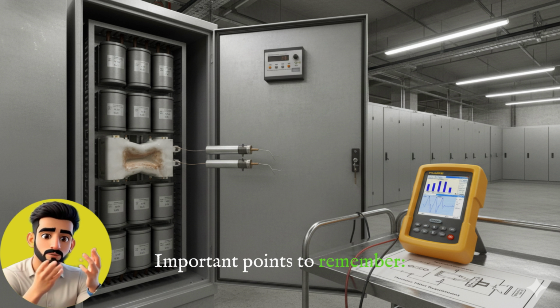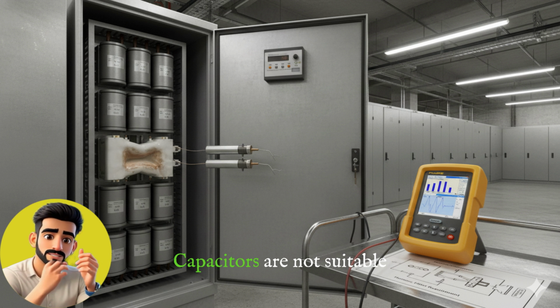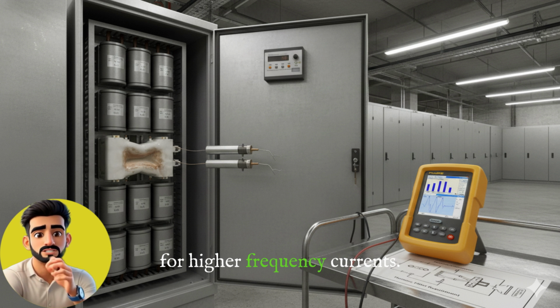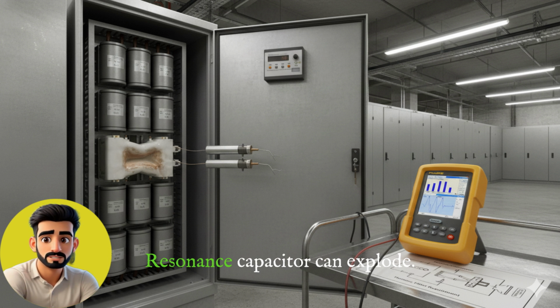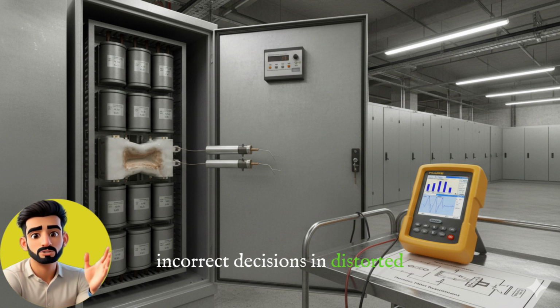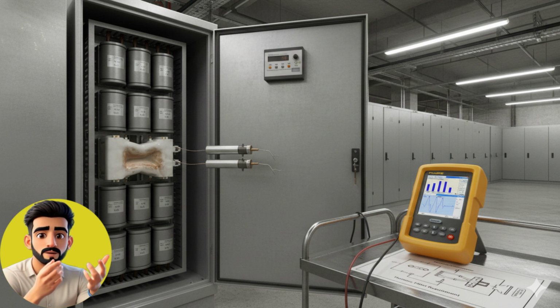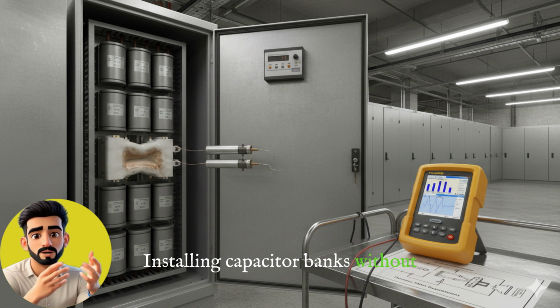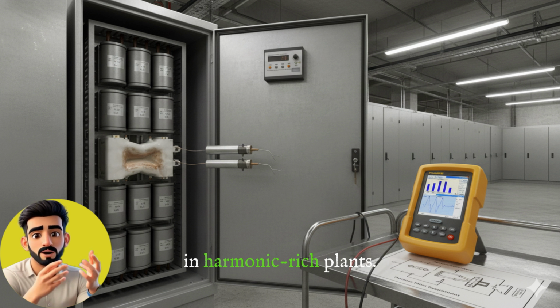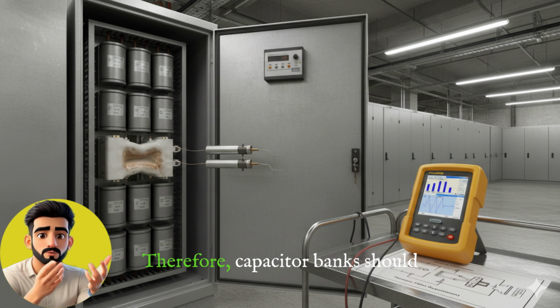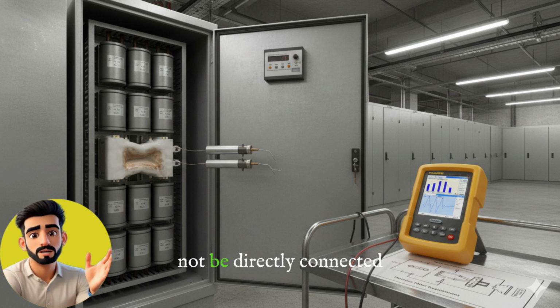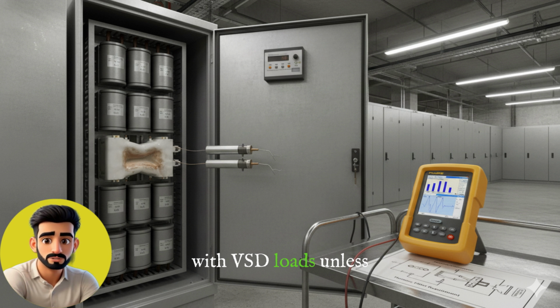Important points to remember. 1. Capacitors are not suitable for higher frequency currents. 2. Resonance capacitor can explode. 3. Power factor controller takes incorrect decisions in distorted waveforms. 4. Installing capacitor banks without harmonic filters is risky in harmonic-rich plants. Therefore, capacitor banks should not be directly connected with VSD loads unless the filter is in series.